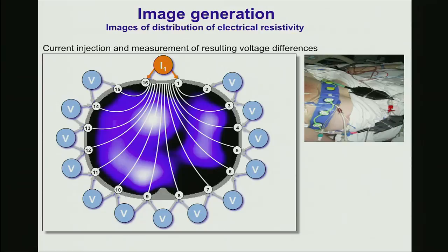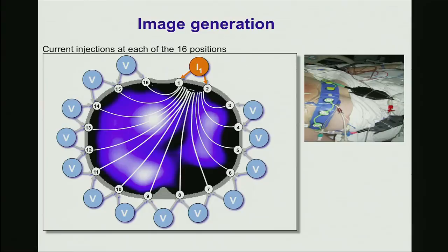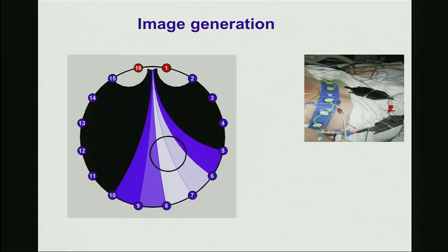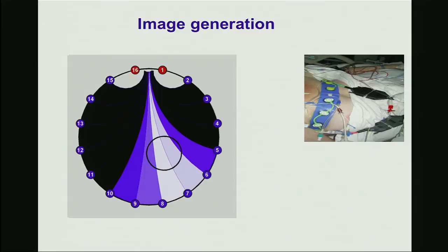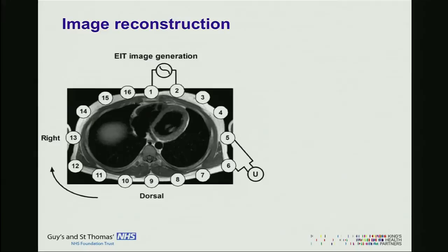One pair of electrodes injects some current, whereas all the other 13 pairs of passive electrodes record a difference in potential in different areas of the lung. When the first recording is done, the next adjacent pair of electrodes will inject, and all the other passive electrodes will record the image. This process is repeated many times, and the whole cycle of EIT is when all 16 pairs have injected and recorded. This happens very fast — 50 times a second — much faster and more responsive than any other technique, and very well suited to finding diagnostic changes in physiology.